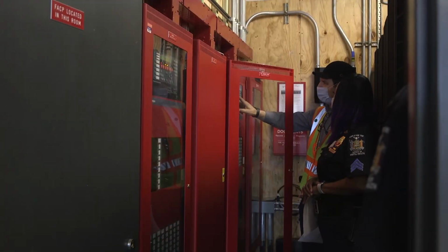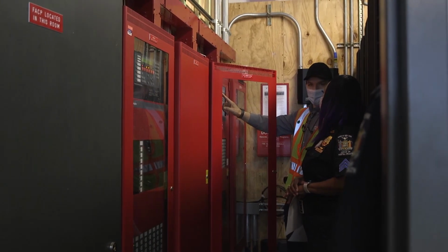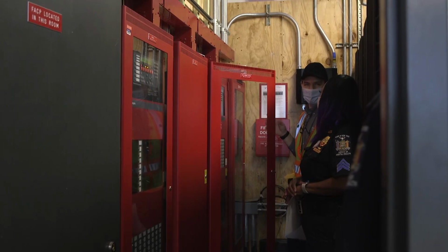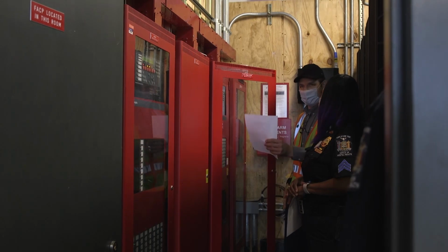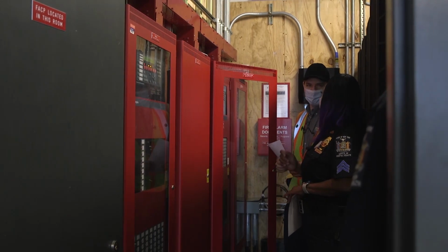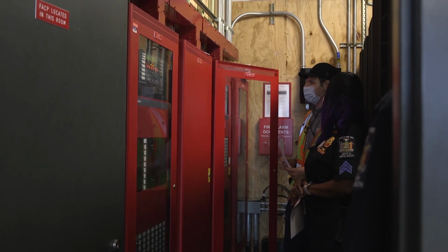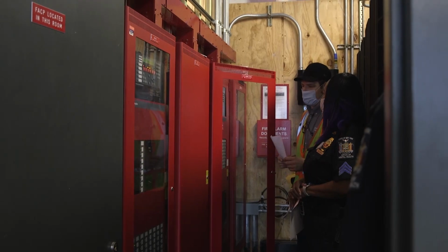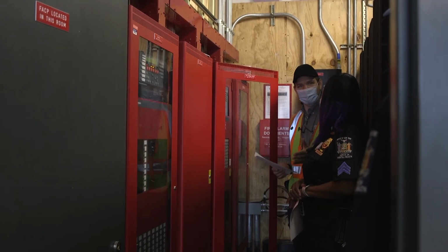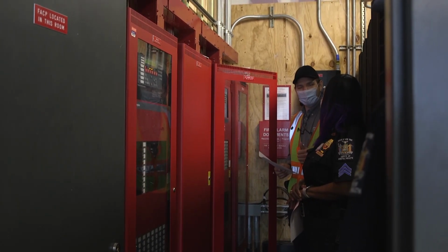So now we come to the panel, acknowledge, and you see, okay, pull station. Pull station, but it's normal. When it's normal, you can reset the system, no problem. If it still says fire alarm, you need to go there and open and close the pull station. Reset. That's another thing I'm gonna show you, because it's very important. A lot of people are breaking the pull station. Somebody pulled the pull station and then tries to close it without a key. No, you cannot. You're gonna break the switch. You have to use your key.